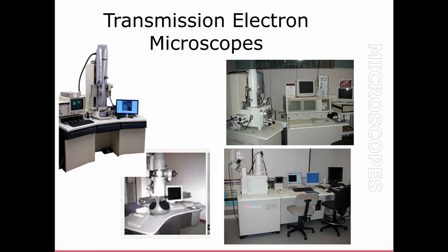The atmosphere in which the electrons are flowing is a perfect vacuum. In other words, it's like space, deep space. There's nothing. I mean, we have ion getter pumps that pull out all the amounts of anything, so it has to be almost perfectly nothing in the atmosphere where these scopes work. I didn't mention that, but that's why it's so expensive. It has to pull it down.